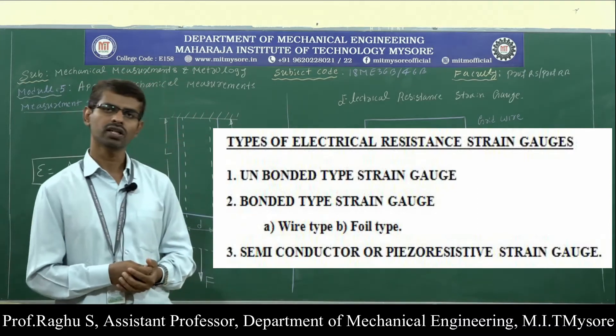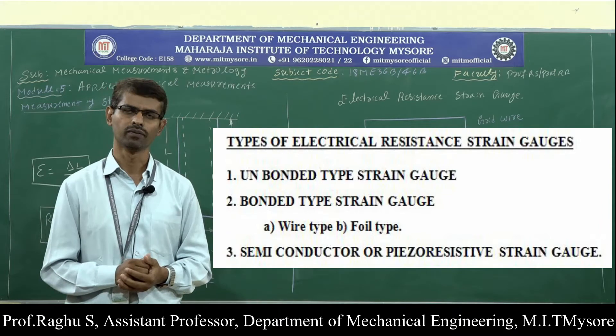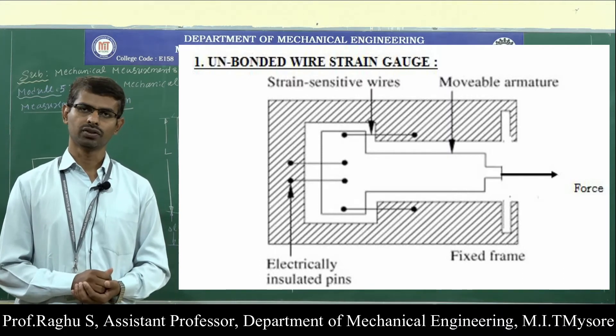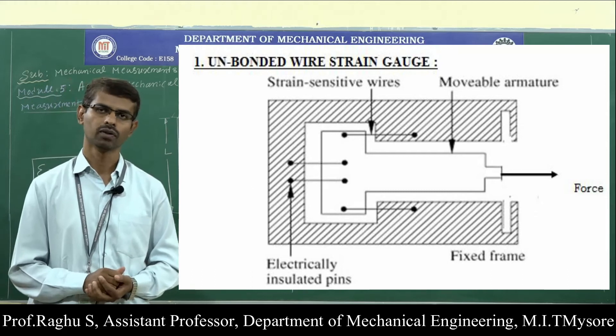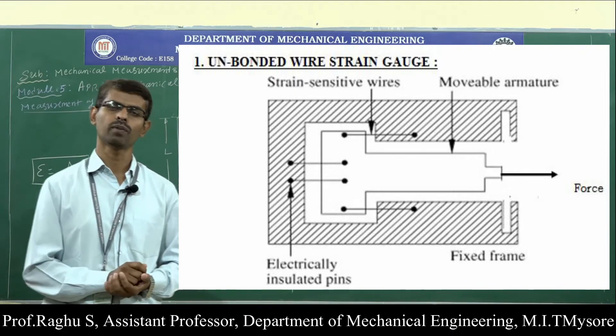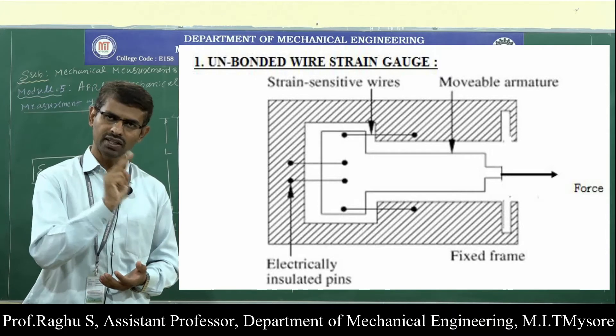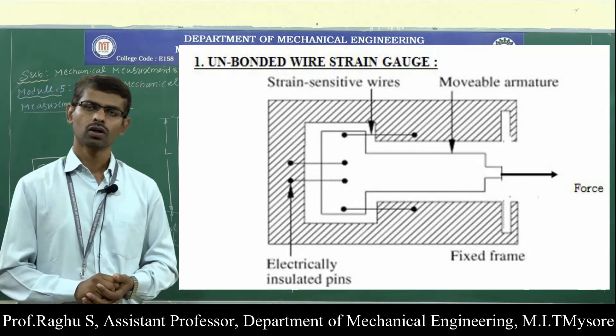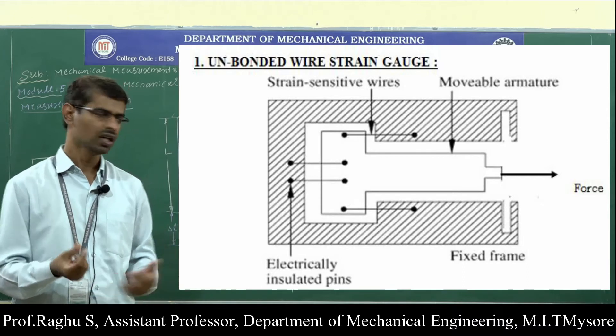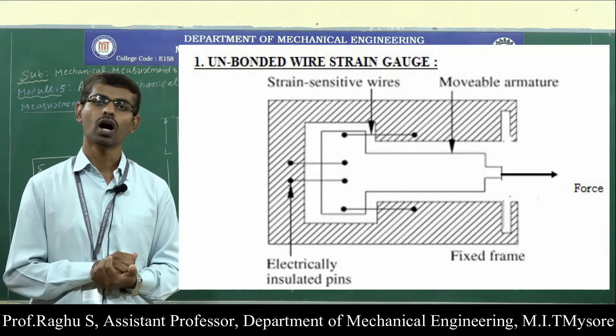Now let us discuss the types of electrical resistance strain gauges. We have three types: unbonded type, bonded type, and semiconductor type. The unbonded type strain gauges do not have any backing material. It consists of a fixed frame and a movable platform. The wires are connected to the fixed frame and movable platform through insulated pins. When the load acts on the movable frame, two wires are in tension and two wires are in compression. Due to deformation, the resistance of the wire changes, and this change in resistance is measured by using the Wheatstone bridge, which can be taken as the measurement of strain.